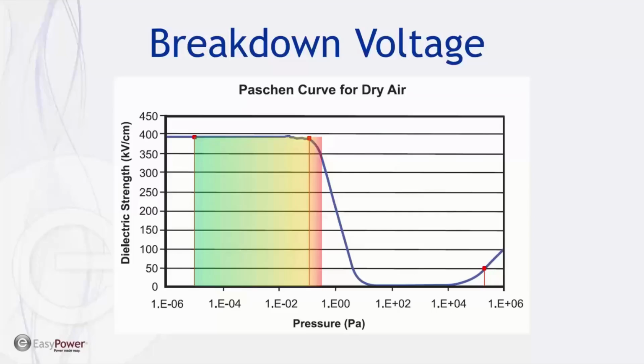So the left two red lines are basically the operating range of a vacuum interrupter, with the far left red line being the approximate pressure at which most vacuum interrupters are sealed when they're new. The difference in pressure between a failed interrupter and a new vacuum interrupter is about 10,000 times. With normal testing techniques, or a high-pot test, the vacuum integrity test is the general name for it, it would tell you that you are either in the operating range or outside of the operating range. But that's all the information that it gives you. It doesn't tell you exactly where in that range you are.